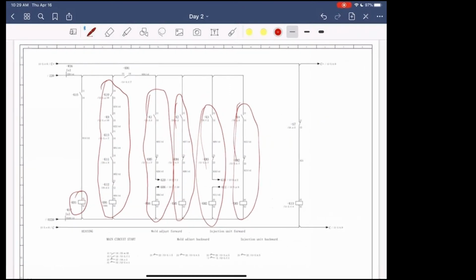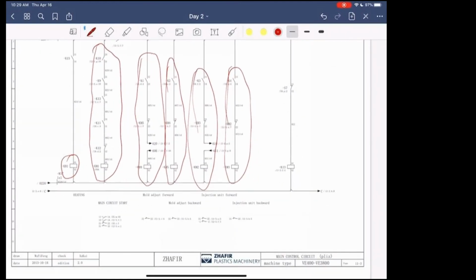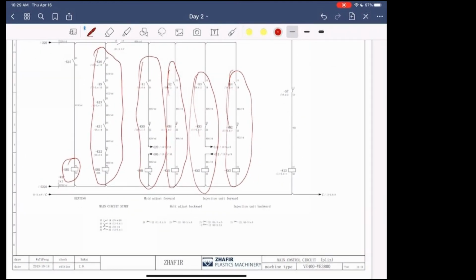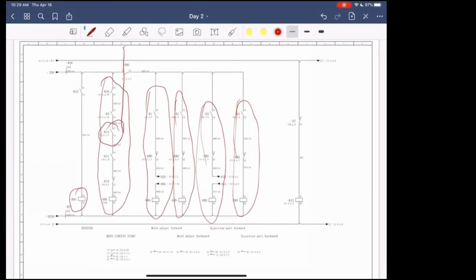And you have this K13, which is on page 11, F4. So we're on page 11. F4 is this guy right here. That's just a safety that's coming off of 24 volts to make sure that the power is okay. It just checks the power for you.